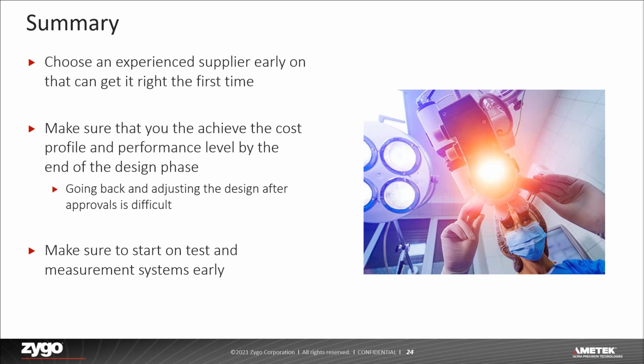Wrapping up, I've covered the process of bringing a medical optic from an initial design up through full-scale production. I've tried to highlight key things to pay attention to along the way. You want to remember that you should work with your supplier early on. Being collaborative through the design process will give you the highest chance for success. Make sure you take manufacturing considerations into your design process. Going back and changing your design after you've received approvals can be extremely difficult. You also want to make sure that you consider your test and measurement system early on. Some acceptance tests may involve more complexity than your optical system itself. Starting on the test and measurement system early will allow you to mitigate having a completed optic waiting on the shelf to get tested.